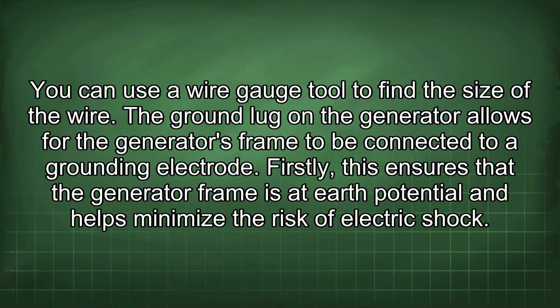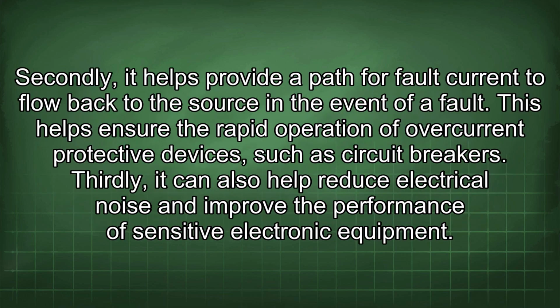The ground lug on the generator allows for the generator's frame to be connected to a grounding electrode. Firstly, this ensures that the generator frame is at earth potential and helps minimize the risk of electric shock. Secondly, it helps provide a path for fault current to flow back to the source in the event of a fault. This helps ensure the rapid operation of overcurrent protective devices such as circuit breakers. Thirdly, it can also help reduce electrical noise and improve the performance of sensitive electronic equipment.